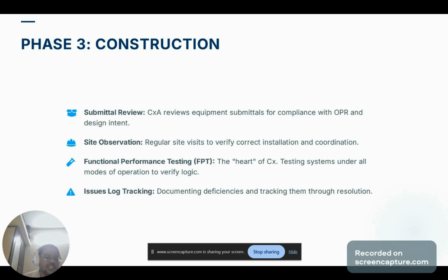Then comes functional performance testing. This is the heart of commissioning. We test the system under all possible modes of operation: normal mode, part load, emergency shutdown, power failure, and seasonal transition, to verify that the control programming and sequence of operations work perfectly.